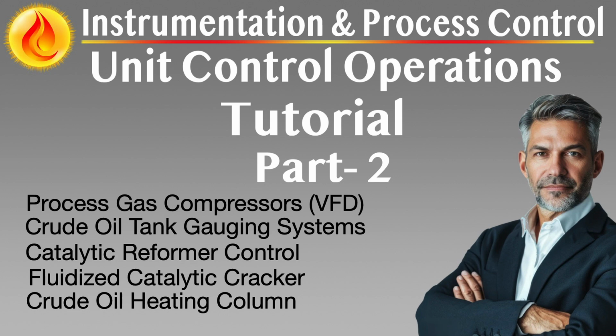Traditionally, compressor control relied on mechanical recycle valves and pressure switches, offering limited adaptability during process swings. VFDs have replaced fixed speed drivers and throttle-based flow regulation with real-time RPM control, enabling smooth, precise modulation of gas throughput based on demand. This approach minimizes pressure fluctuations, reduces recirculation losses, and avoids the inefficient energy profiles typical of mechanical throttling, particularly at partial loads.